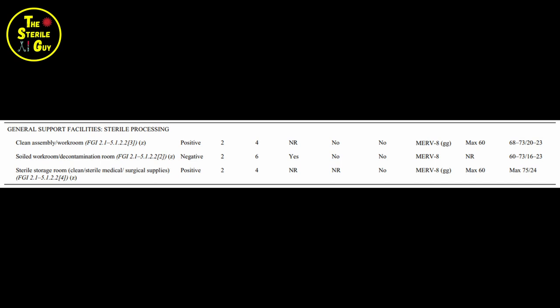The clean areas of assembly and storage require only four air exchanges per hour. Since decontam is much dirtier, it requires six air exchanges. Now that we've covered what air exchanges are, that'll make it much easier to describe and show you what negative and positive air pressure means — not only in a single room, but as a department as a whole and how it works together.